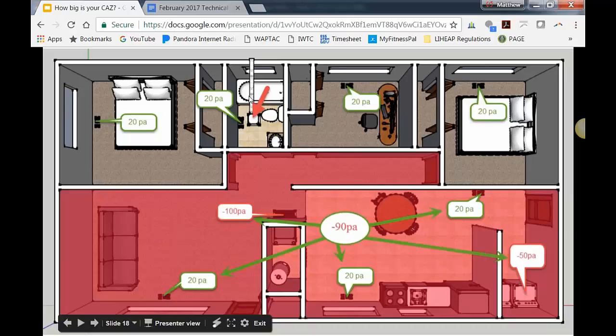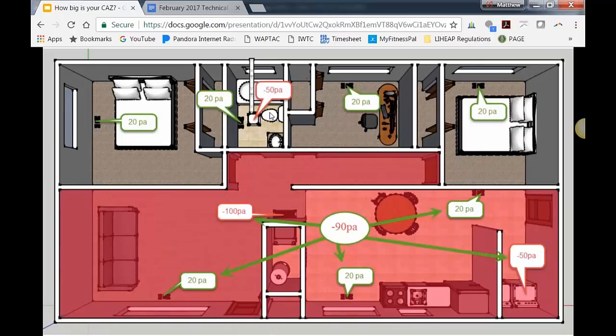So what do you think would happen to the pressure in this bathroom if it was at 20 pascals and now we have an exhaust fan in it? It depends on how much you're pulling with your fan, but it should go more negative. Yeah, it's probably going to drop, and I've exaggerated this again and said, okay, let's say it's moving 50 pascals of pressure, so we have this massive fan. It's one of the big fans. Anyway, so we now have a change in pressure, and it's caused this little room to go, let's say, negative 30 in our little sterile environment, right?